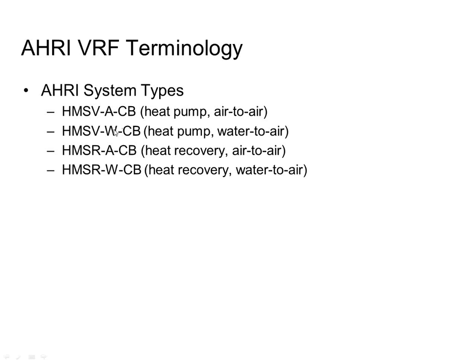The fifth digit is either an A or a W. A means it's an air-to-air heat pump. A W means it's a water-to-air heat pump. Right? That's the difference there. So do I have air as my sink source, or do I have a water loop, meaning a cooling tower and boiler, or even a ground source geothermal loop connected to my system? So V or R means heat pump or heat recovery, three-pipe system. A or W means air or water.